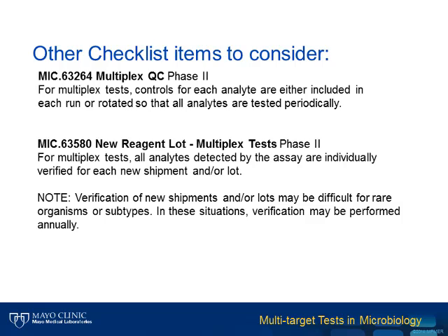For new lot verification, a good strategy is to run two controls that are each positive for half of the analytes, such that each analyte has a positive and a negative control. For instance, control mixture A may contain organisms 1, 3, 5, 7, and 9, and control mixture B would contain organisms 2, 4, 6, 8, and 10. That way, within two runs, you've tested positive and negative for each target. Also, for new lot verification, each analyte must be tested with each new lot to assure that each target is working.